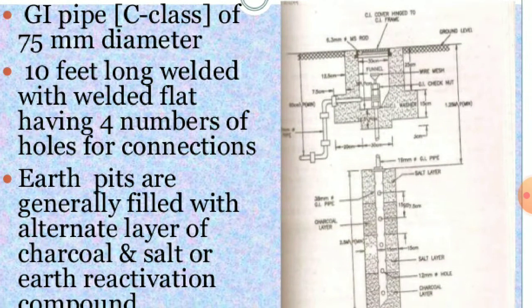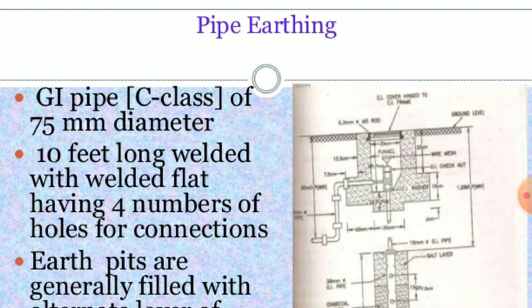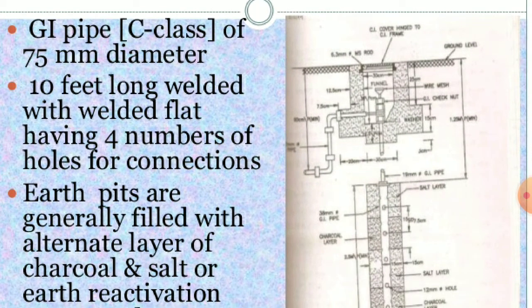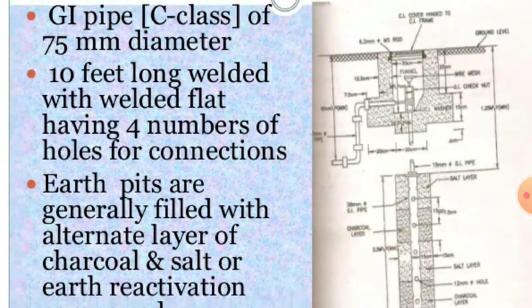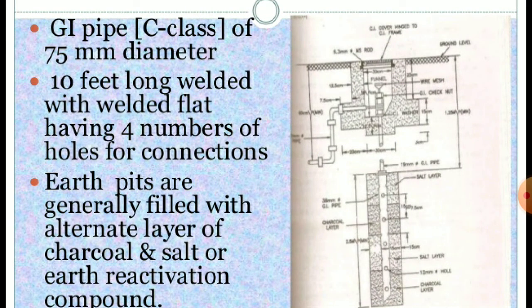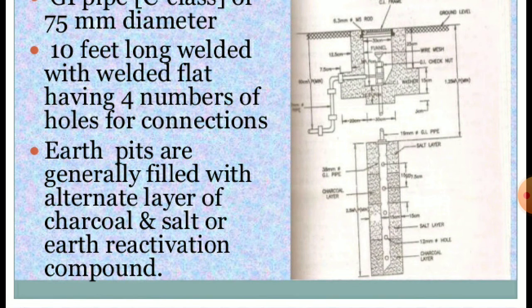Here a small picture is provided, which indicates the pipe earthing method. In pipe earthing, we take a pipe. We can prefer galvanized iron, or we can prefer copper also, because they possess very low resistance. So we take a galvanized iron pipe, or a copper pipe, of 75 mm diameter. That 75 mm diameter pipe is buried in the ground 10 feet below the earth level, and it is provided with 4 holes for external connections.